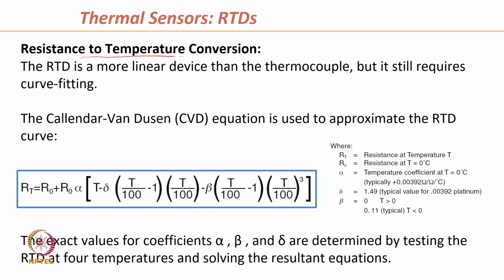Now, resistance to temperature conversion. This RTD is a more linear device than the thermocouple, but it still requires some curve fitting. The CVD equation, or the Callendar-Van Dusen equation, is used to approximate the RTD curve, which is given here: RT equal to R naught plus R naught alpha T minus delta T upon 100 minus 1.